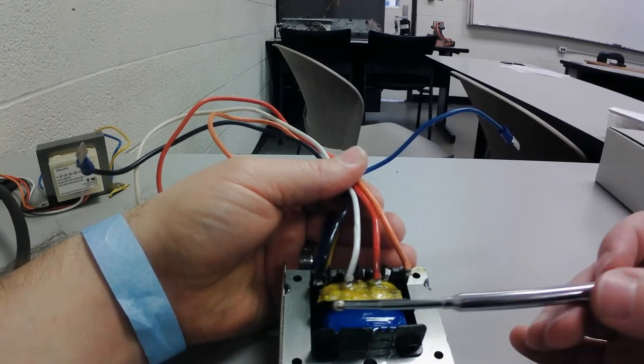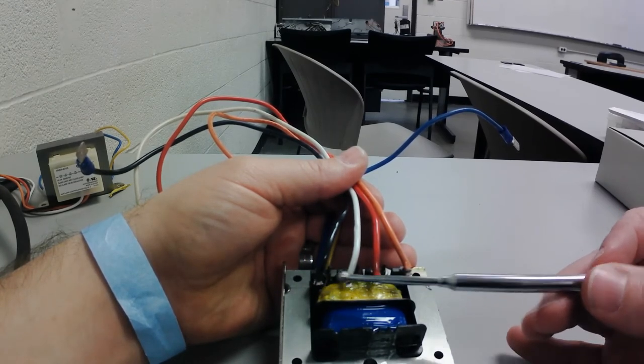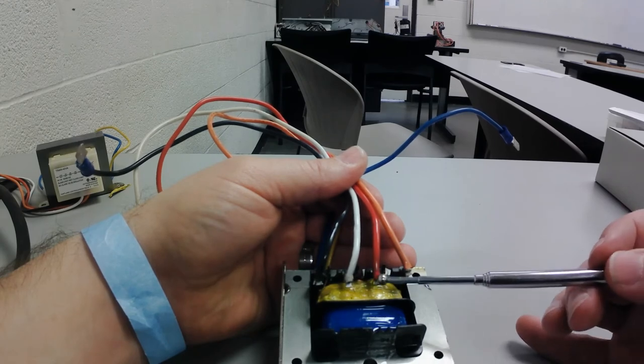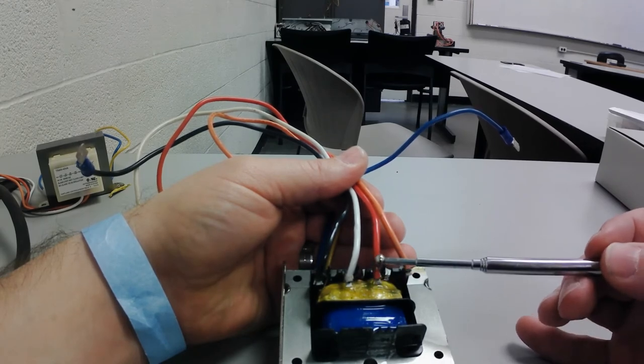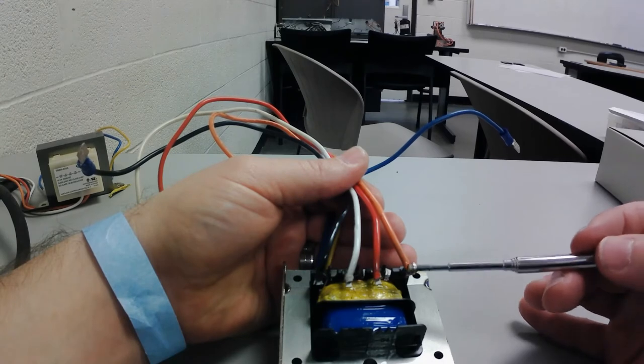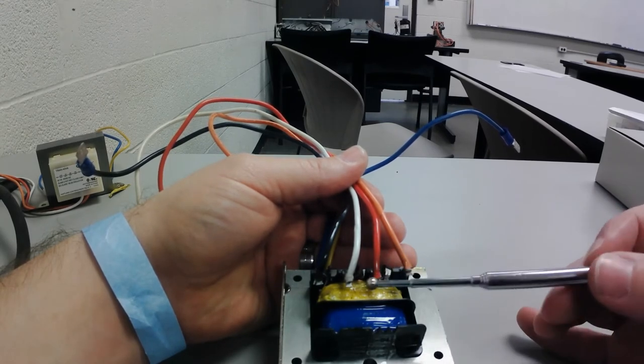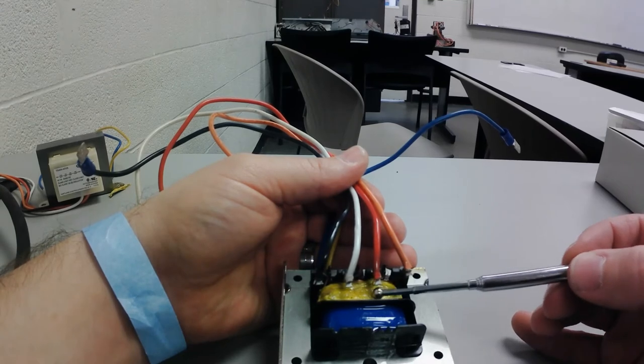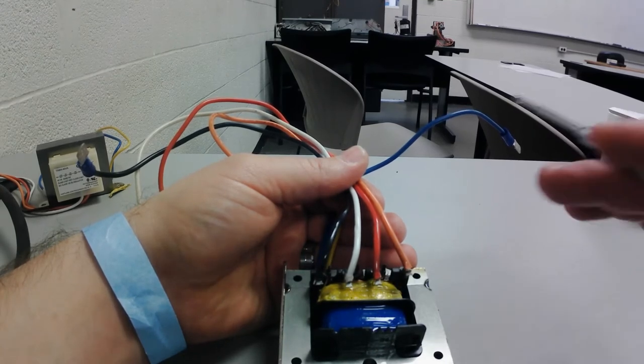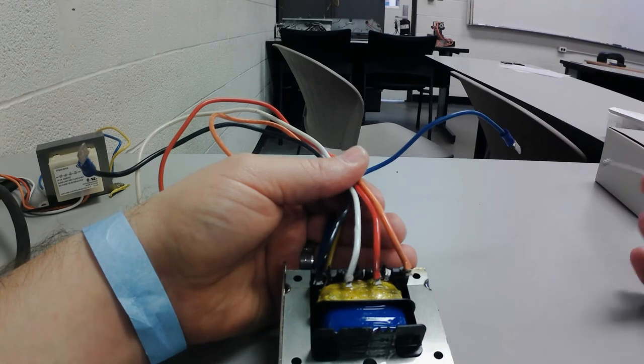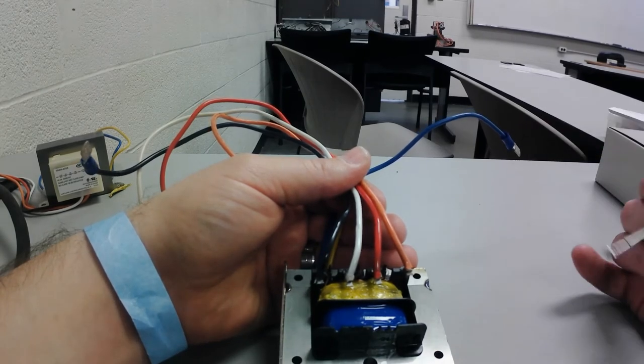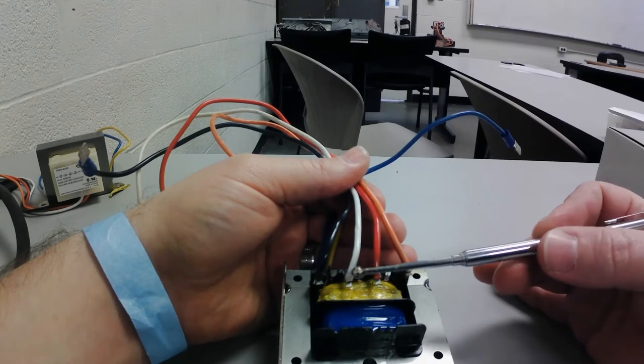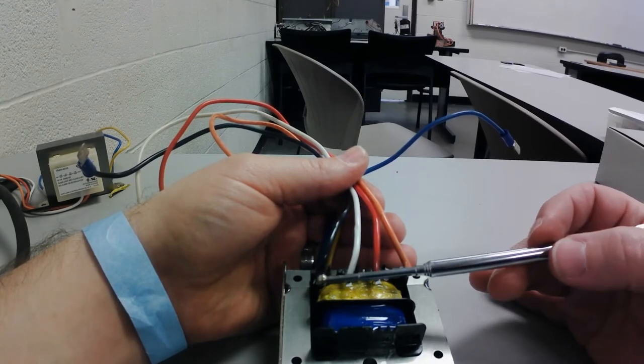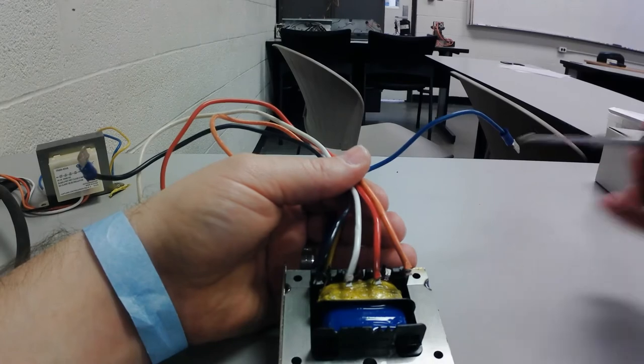So what I'm doing right now is I'm only applying 120 volts to the white and the black wires. So why did I get 211 on the 208, the red wire? And why did I get 244 on the orange wire? That's because these wires are still connected in the winding, okay? It's not that you get to pick what you want and the others just go unused and no power. They go unused, but they still carry that potential, and you have to be aware of that, okay?